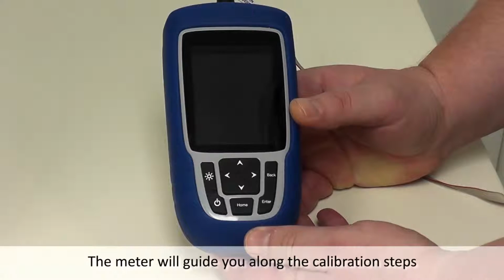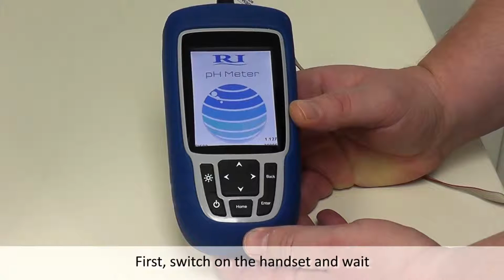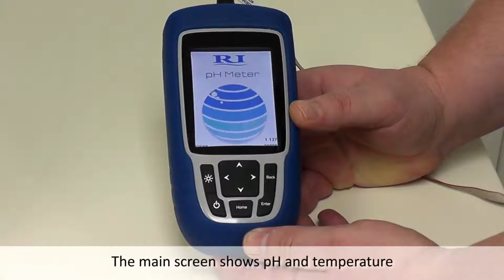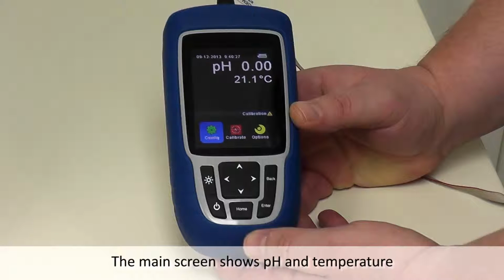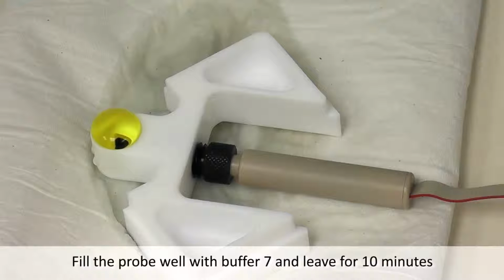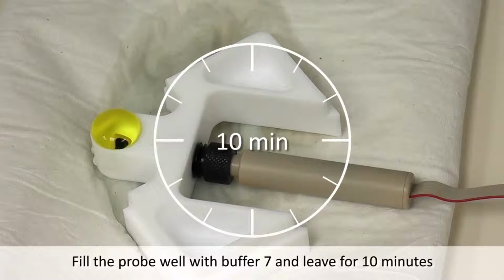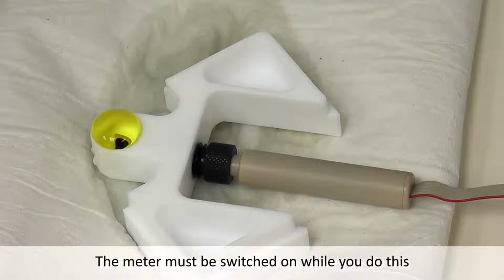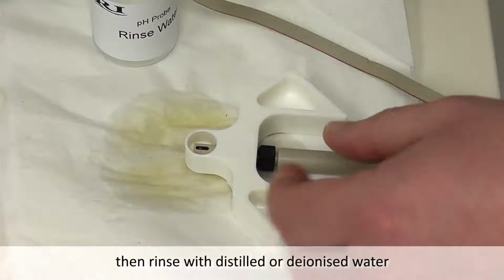The meter will guide you along the calibration steps. First, switch on the handset and wait. The main screen shows pH and temperature. Fill the probe well with buffer 7 and leave for 10 minutes. The meter must be switched on while you do this. Then rinse with distilled or deionized water.